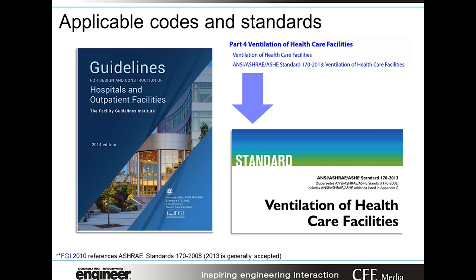The Facility Guidelines Institute publishes guidelines that help planners, designers, and builders understand expectations of modern healthcare facilities. The 2014 edition contains specific criteria by which designers measure volumes of air, filtration requirements, air changes, and humidification requirements. These technical elements are informed by ASHRAE Standard 170, the guidebook for HVAC designers for healthcare facilities. We'll be focusing our talk primarily on expectation criteria largely driven by information in this standard.